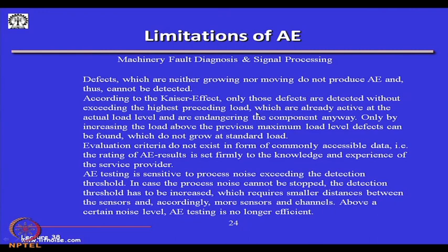There are certain limitations of acoustic emission. First, defects which are neither growing nor moving do not produce AE and thus cannot be detected. According to the Kaiser effect, only defects already active at the actual load level are detected without exceeding the highest preceding load. Only by increasing the load above the previous maximum can defects be found that do not grow at standard load. AE testing is also very sensitive to noise — noise cannot be stopped and we must be very careful about signal-to-noise ratio.